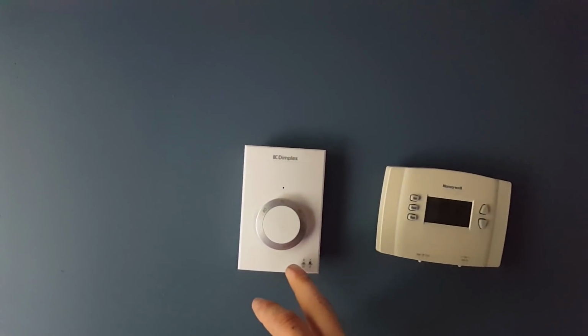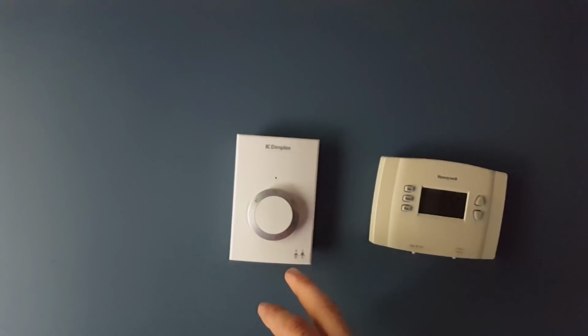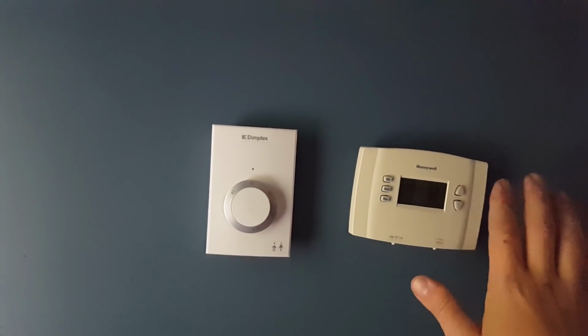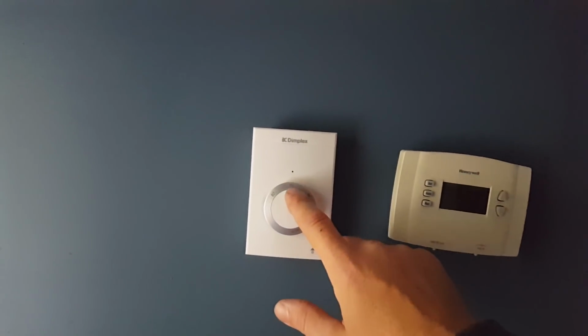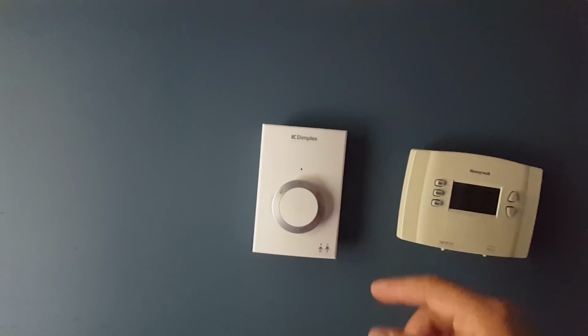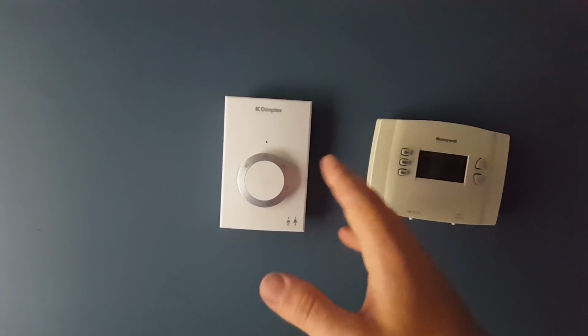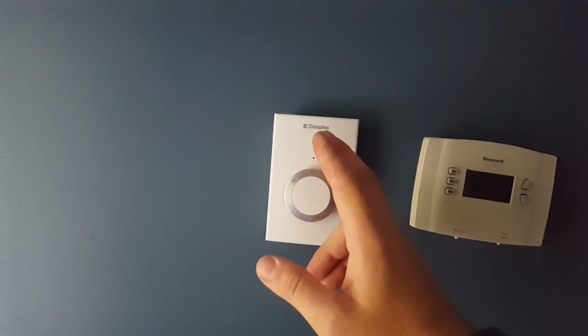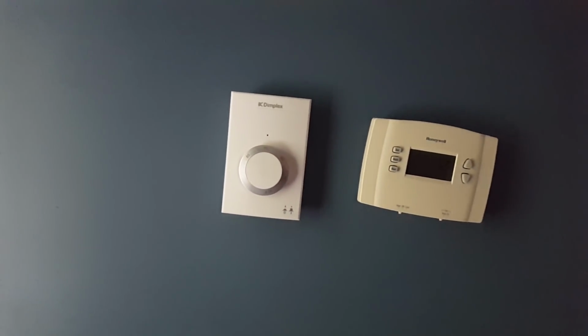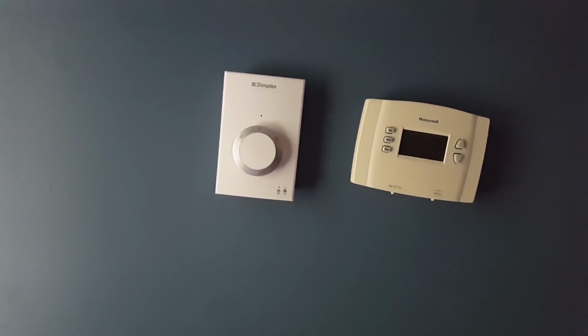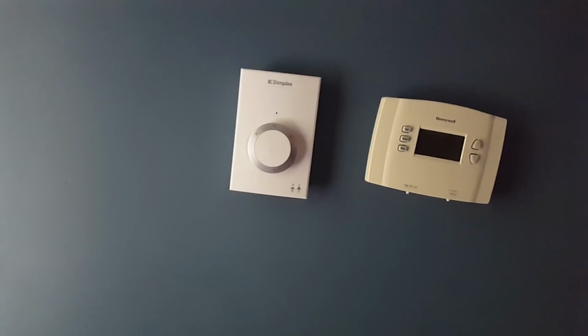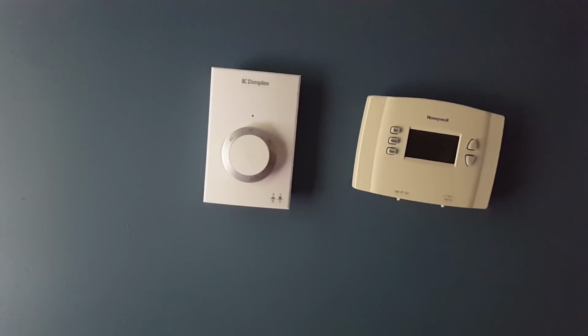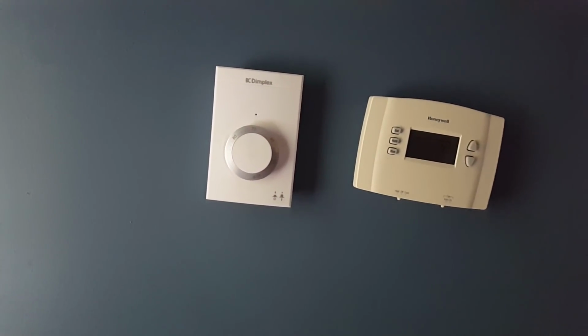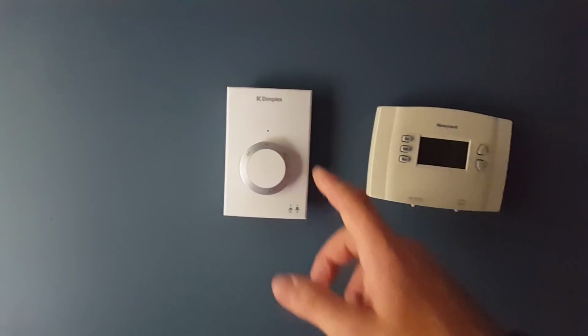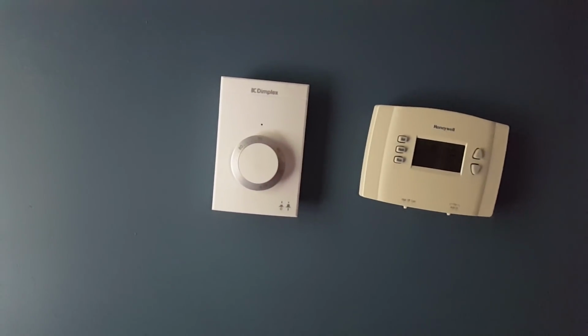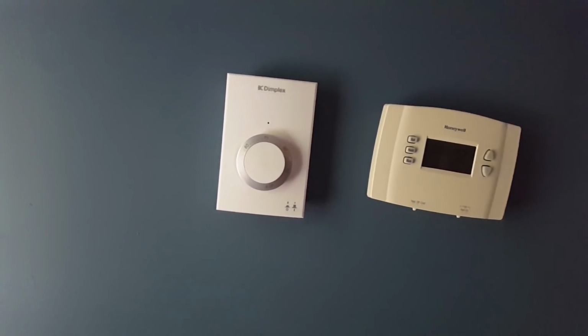This second thermostat is for the actual boiler, the outdoor wood burner. Since it's kind of turned off right now, it doesn't really matter, but I have it set at whatever temperature you want—right now about 70. When it gets below 70 degrees in the house, this trips on and the blower kicks on in the furnace. Just the blower comes on and blows air over the heat exchanger with all that hot water in it, heating the house. Then once it's satisfied at 70 degrees, it kicks off and the blower goes off.